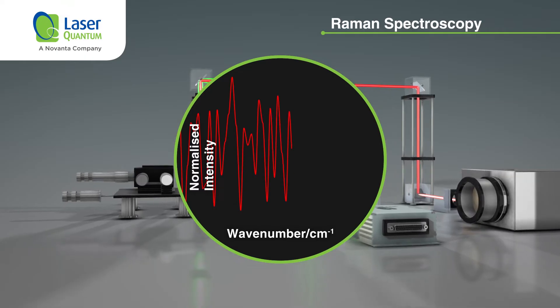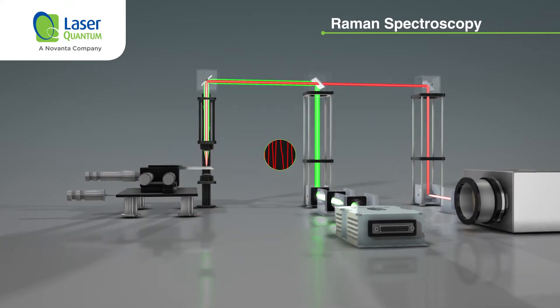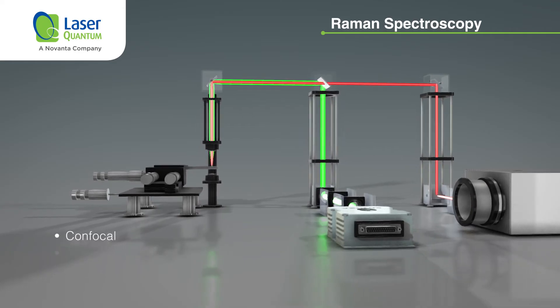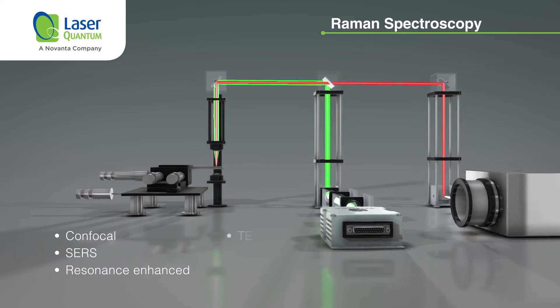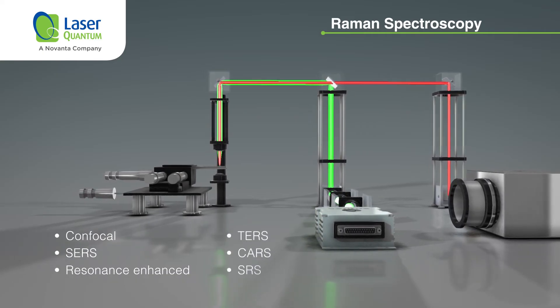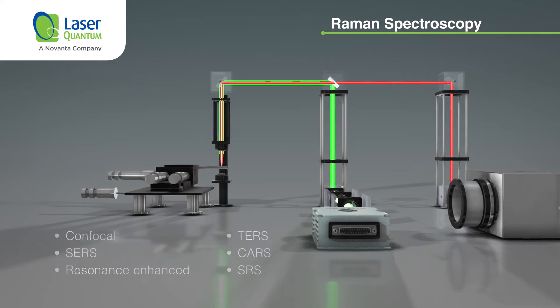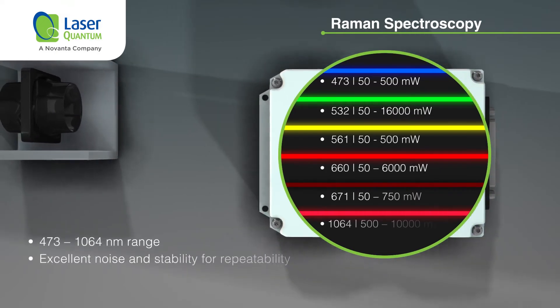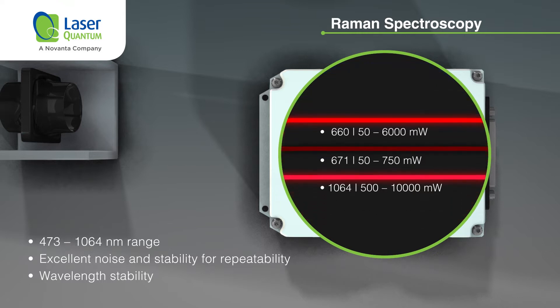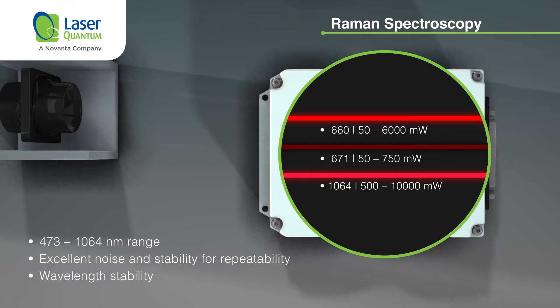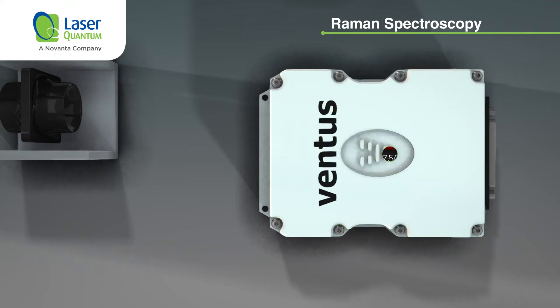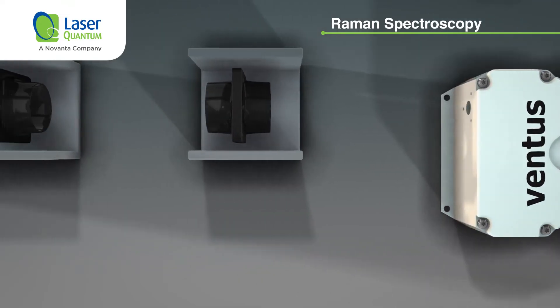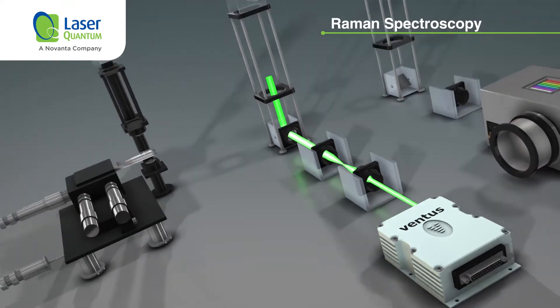There are several variants of Raman, including confocal, SERS, resonance-enhanced, TERS, CARS, and SRS. Wavelengths commonly associated with Raman range between 473 and 1064 nanometers. Laser Quantum's 660, 671, and 1064 nanometer systems are ideal longer-wavelength alternatives for any samples for which fluorescence is an issue, as specific test samples require different specifications.